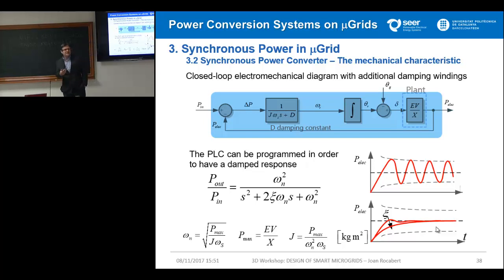Okay, necessary in order for the machine to get a damped response. Now this damping parameter - this is a very superficial definition, don't be so specific - this damping you get as a constant in your code, and this constant in your code you can define the value that you want. So finally, if your system, if your converter, gets oscillations with the power being injected to the grid, change online that damping constant or damping variable, in order that you can impose the system response as damped as you want, as the secondary control imposes, as the microgrid central control imposes.